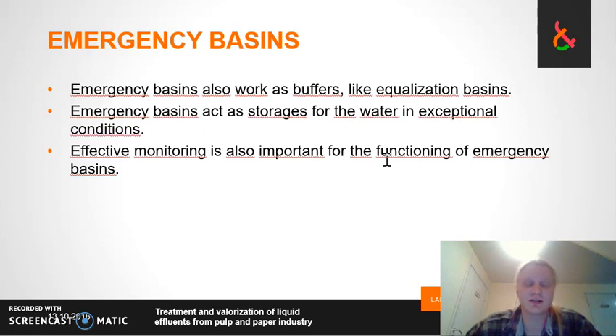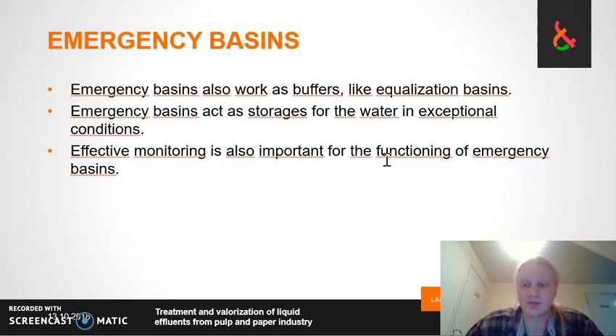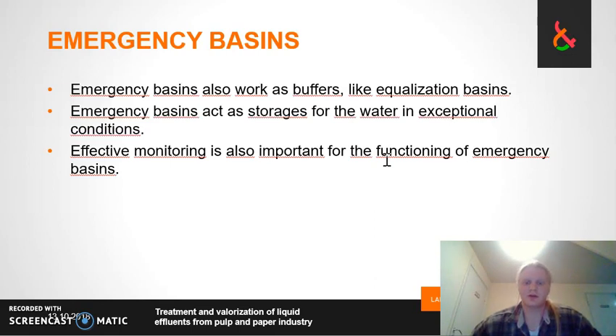One study says that usually a spill is noticed 12 to 24 hours later, which is pretty much too late. So if that is the speed of information, then these emergency basins could only be used for exceptional conditions that can be foreknown, such as service and maintenance situations. Effective monitoring would enable us to use these basins effectively whenever there is a harmful substance or too high a concentration of some matter in the wastewater.